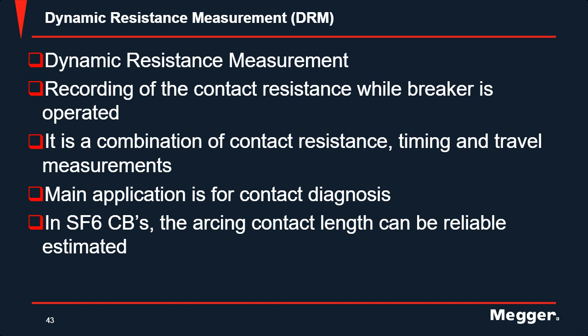This test is conducted by injecting a DC current through the breaker main contact and measuring the voltage drop and the current while the breaker is in an operated state, so if it's opening or closing. The breaker analyzer, your circuit breaker test set, then calculates and plots the resistance as a function of time. If you do contact movement, so if you're using your transducer and it's recorded simultaneously, you can read the resistance at each contact point, and this method is used to diagnose the life of your arcing contact.